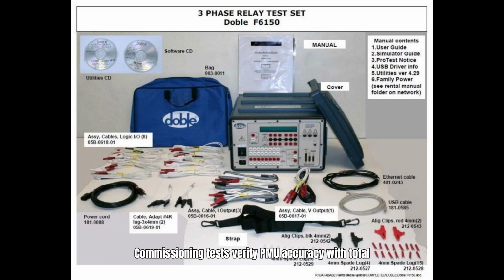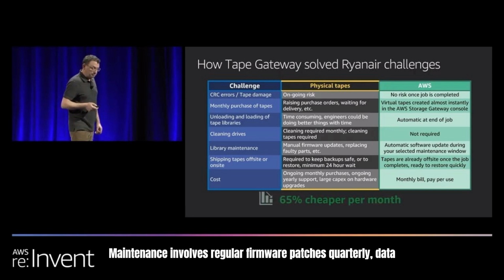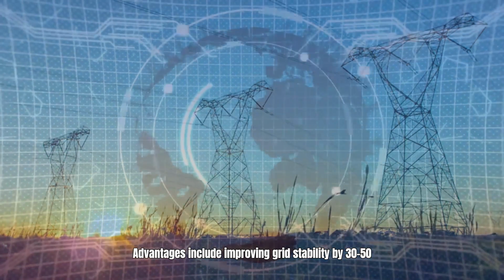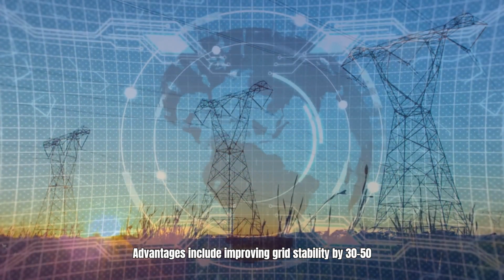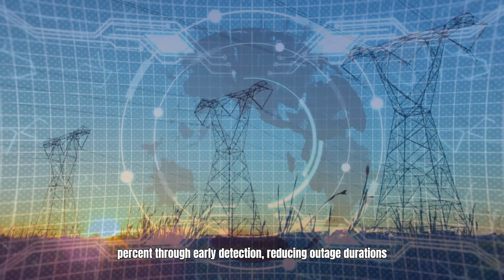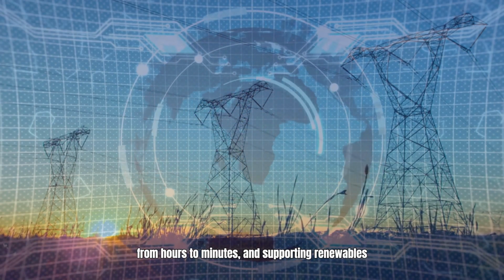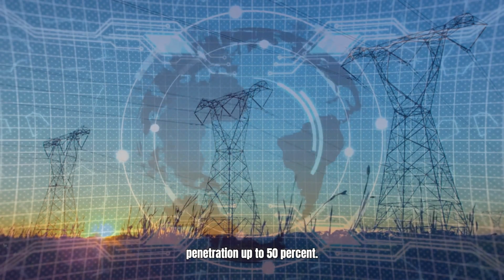Commissioning tests verify PMU accuracy with total vector error below 0.5%, time synchronization error less than 1 microsecond, and end-to-end latency under 100 milliseconds using test sets like Doble F6150. Maintenance involves regular firmware patches quarterly, data integrity verification through CRC checks, and automated backups to cloud storage like AWS S3. Advantages include improving grid stability by 30 to 50% through early detection, reducing outage durations from hours to minutes, and supporting renewables penetration up to 50%.